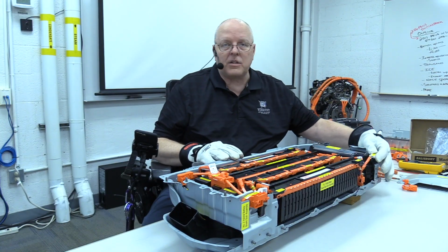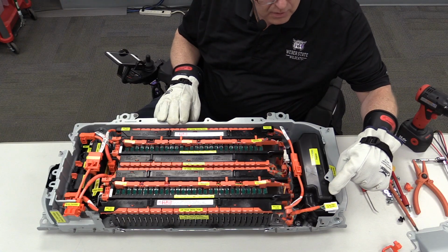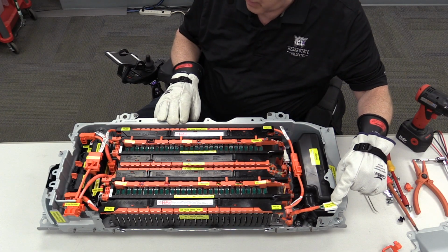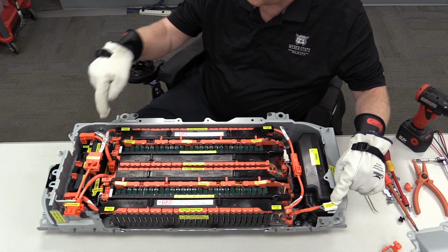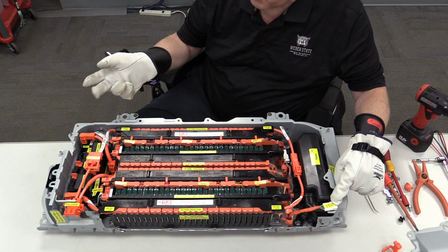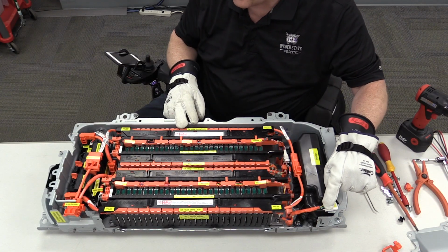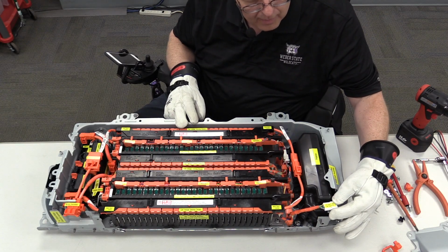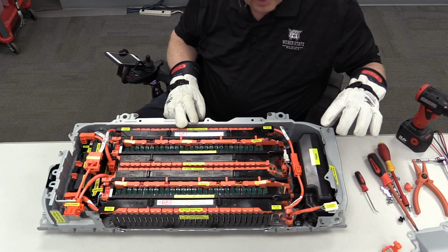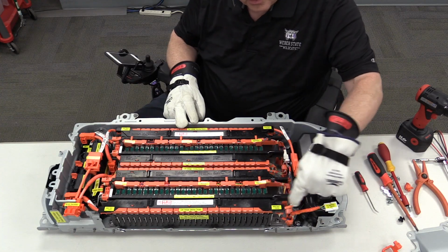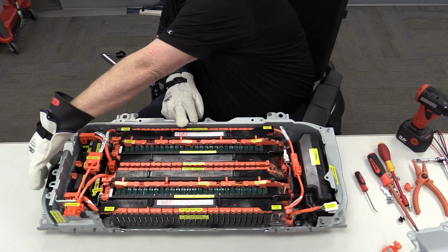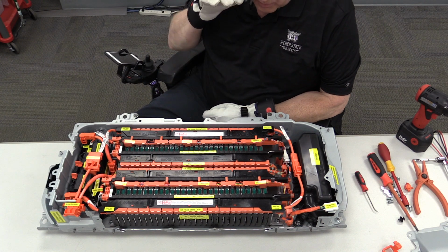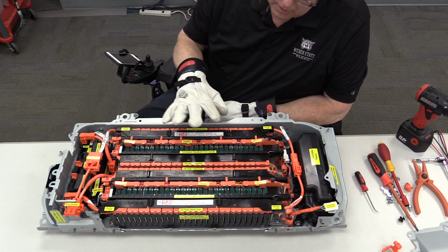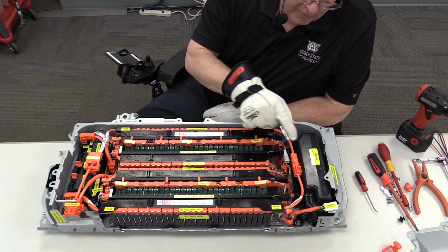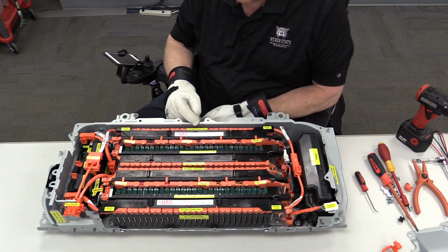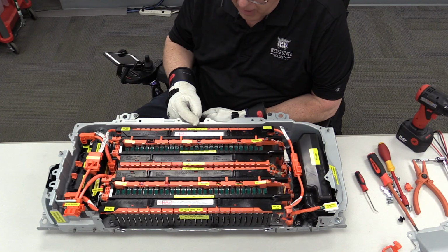We have an electrical connection right here that connects 12 volt power and ground. And remember, the 12 volt system, the low voltage system, is what controls our contactors. It turns them on, turns them off. We have two different CAN lines, a CAN 1 and a CAN 2. And then we have fan control outputs from the battery ECU through the main harness over to the fan itself. And we'll look at that fan a little bit later. So that fan is controlled by the computer here in the driver's side of the battery.